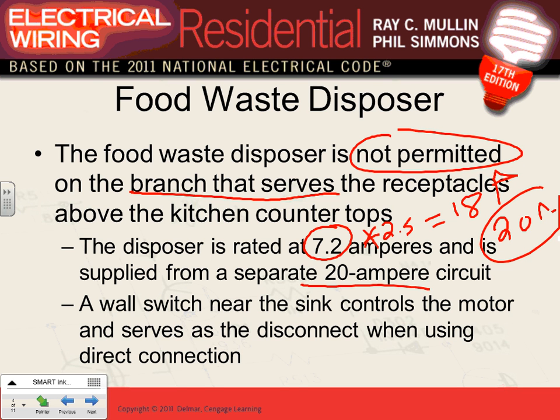Guys, the way they size the conductor is 1.25. Multiply this by 1.25 and give me the answer, will you? 1.25 times 7.2, what do you get? 9 amps. Now, I could have gotten away with number 14, since it's dwelling and residential, all this stuff, guys. And a good idea is we went to what? Number 12. So we went with 12-2 to feed all this system.